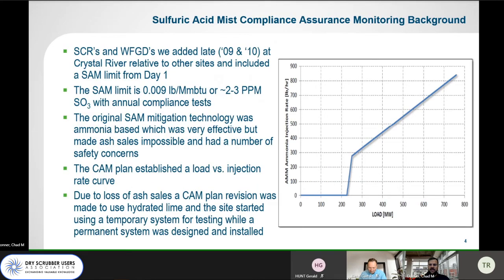So they have a sulfuric acid mist compliance assurance monitoring limit. How that came about was that the SCRs and wet FGDs installed at Crystal River were put on late in the game, in the 09 to 10 time frame. With the addition of those air pollution control devices, a sulfuric acid mist limit was in effect from day one of that equipment being installed. Their SAM limit was 0.009 pounds per million BTU, which equates to about 2 to 3 ppm at the stack, and they complied on annual compliance tests.